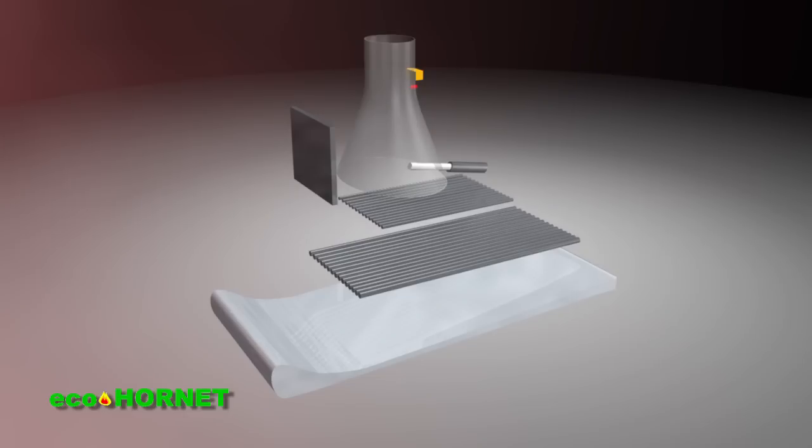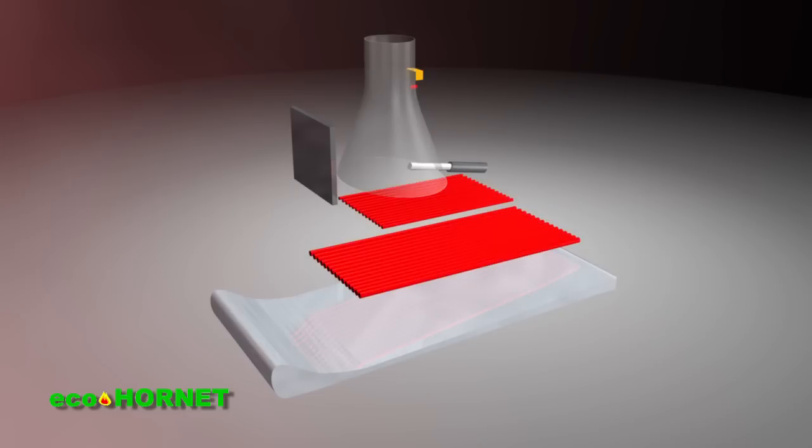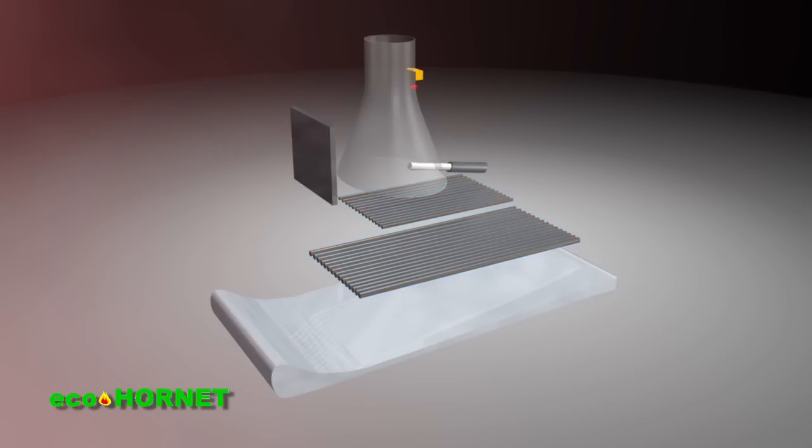The burner is formed of three grates, two of which ensure constant circulation for the combustion of 6 mm pellets, and the third holds the incandescent pellets until their diameter is reduced below 3 mm. It also helps to increase combustion efficiency and reduces the amount of ash.